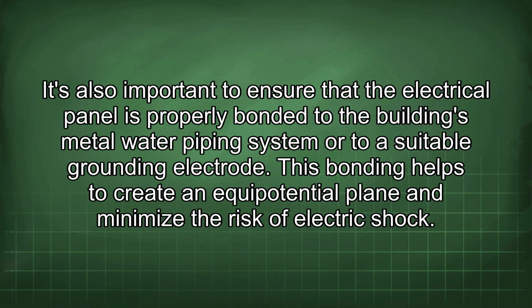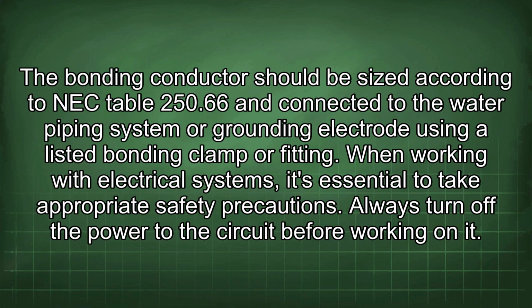It's also important to ensure that the electrical panel is properly bonded to the building's metal water piping system or to a suitable grounding electrode. This bonding helps to create an equipotential plane and minimize the risk of electric shock. The bonding conductor should be sized according to NEC Table 250.66 and connected to the water piping system or grounding electrode using a listed bonding clamp or fitting.